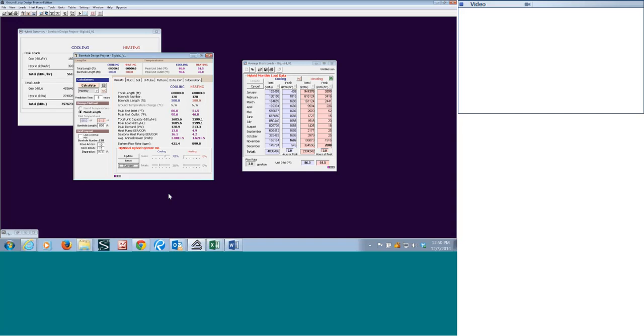We actually talked with one controls contractor on a school, and he said, well, heat pumps don't work in cold weather, so I made a change in the controls to bring in the auxiliary strip heat before the heat pump came on. I was shaking my head. And of course the customer was paying for that extra cost, and they were blaming us in the loop field.